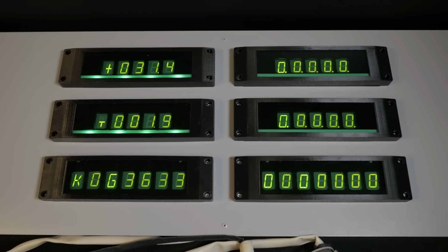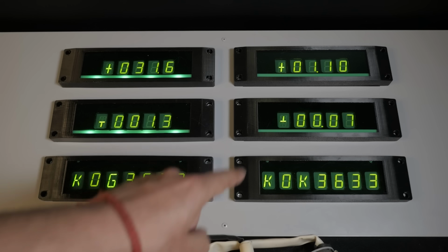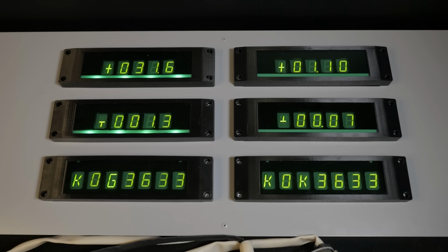And so the operator needs to check several related parameters. K0K gives us the boiling crisis margin for that particular channel. Here the rule is the same: the result must remain greater than 1. A value of 1.25 is normal, and at 1.03 the alarm will activate. Or we can retrieve the power of this channel in megawatts. And by analyzing these parameters the operator can then understand what action is actually needed.